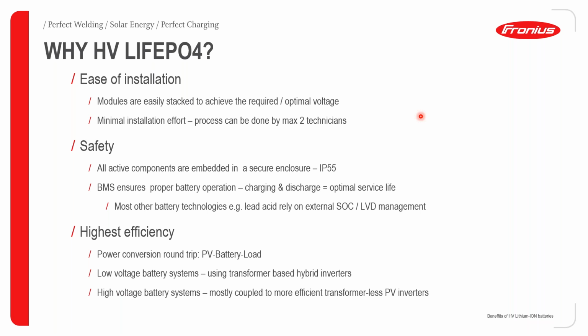So you can start with just a few modules which are stacked to achieve the required operation voltage, depending on the inverter that you're going to connect. If you look at the Gen 24 inverter, there is a recommendation of the minimum battery voltage that the inverter is able to work with, as well as a maximum. This guides you in terms of the minimum number of modules that you need for this battery, as well as the maximum number of modules that you can use per Gen 24 inverter variation. The installation effort is also minimal, and therefore this process can be done by a maximum of 2 technicians.